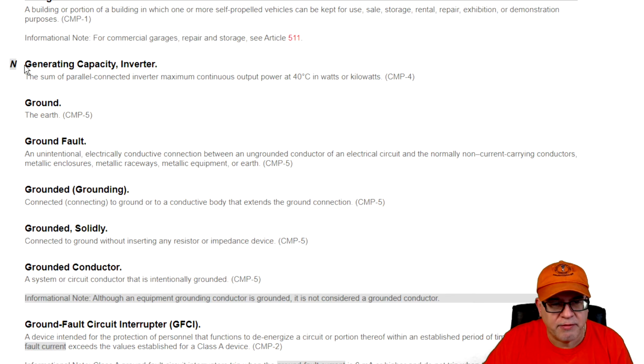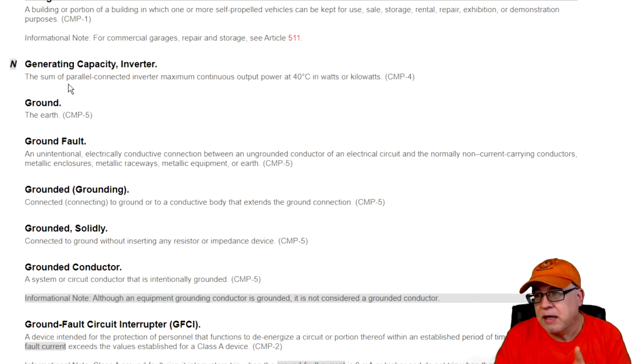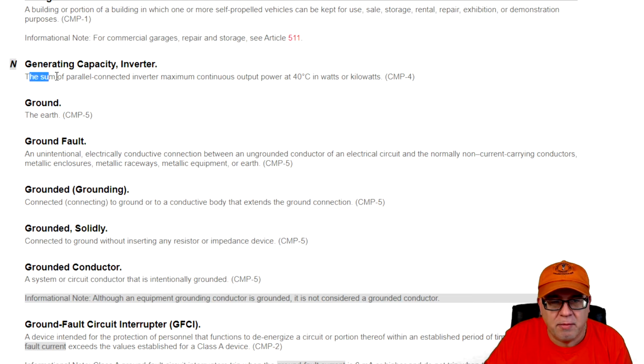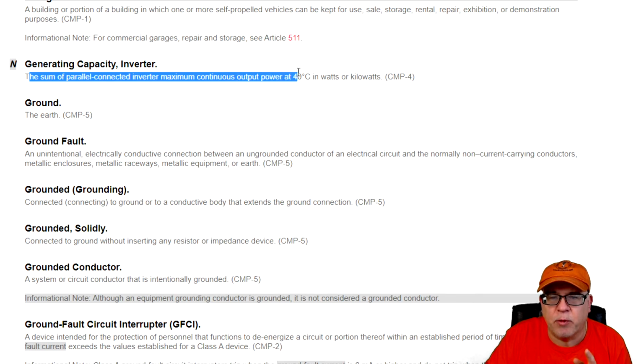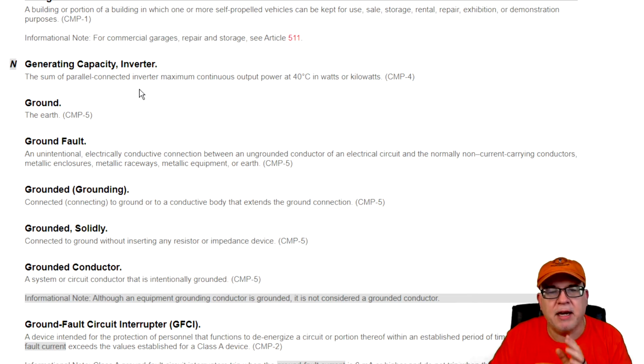We have a new definition here called inverter generating capacity. And what does that mean? When the code talks about this potentially up in, I guess it would be, 690 or other areas like that, it might have a question about an inverter's generating capacity. And of course, it's the sum of parallel connected inverters' maximum continuous output power at 40 degrees C in watts or kilowatts. Okay. Again, we'll talk about that when we get up there and how that would apply. But this is where you have parallel connected inverters, and you're looking at the maximum continuous output, which is posted on the inverters.